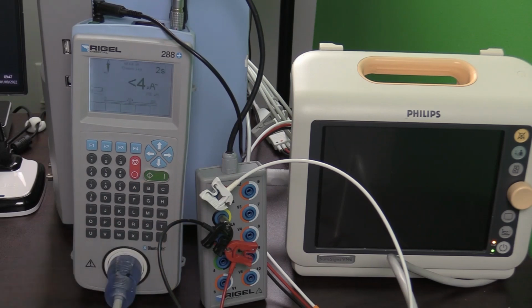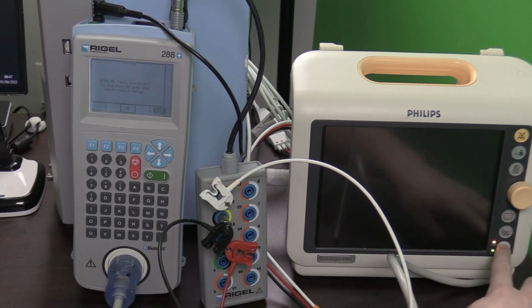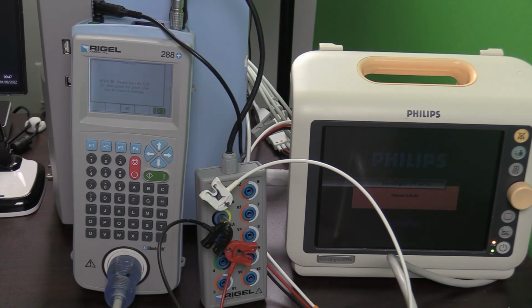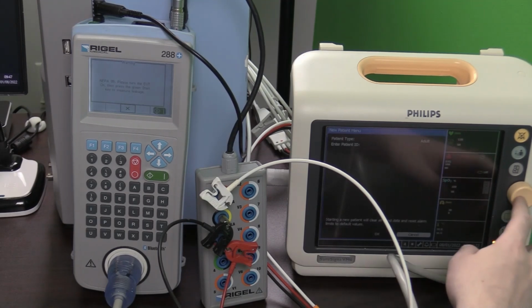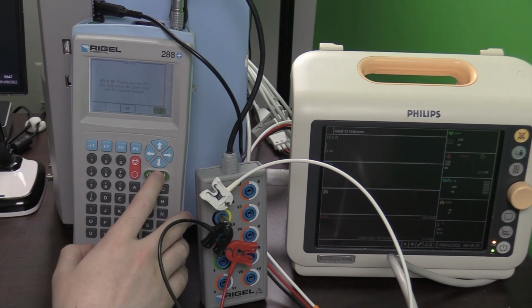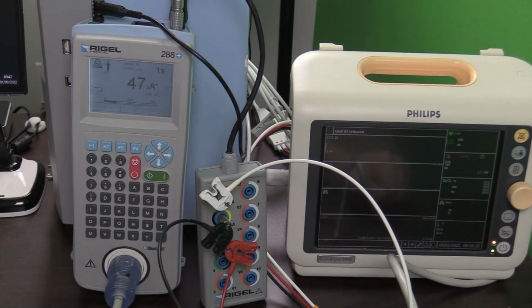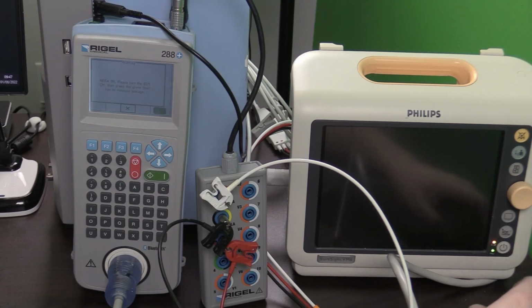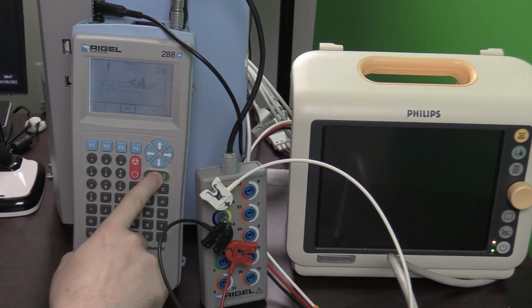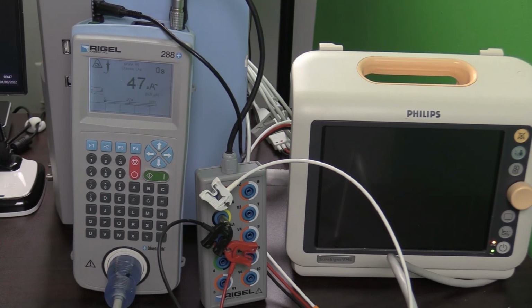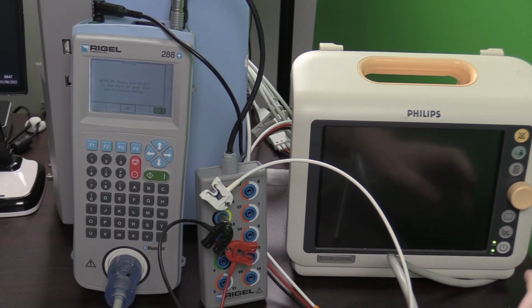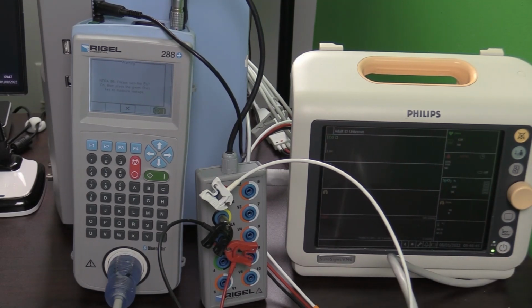Now that the monitor is off, I can run the next test. And now I can turn the monitor back on to continue on the test. And as this auto test is running, it is going step by step through every NFPA test that we have already done in manual mode and automatically saving the results in the device. All the user has to do is turn their device under test on and off when prompted and hit the green button when prompted.